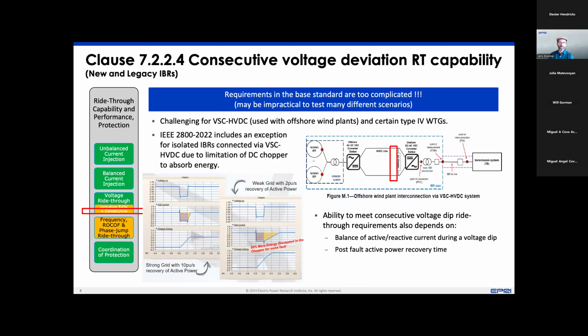Now, on the other hand, consecutive voltage deviation ride-through capability, and this is what Miguel already summarized here, is quite complicated, actually, as defined in the standard. So a future revision of this very first edition of the standard could potentially improve that section further. And we also would like to highlight the fact that the requirement includes an exception for isolated IBRs that connect via VSC HVDC due to the limitation of the DC chopper to absorb the energy. And 2800 includes an annex in which a full rated power output over 2 seconds is considered one possible design criterion for VSC HVDC.